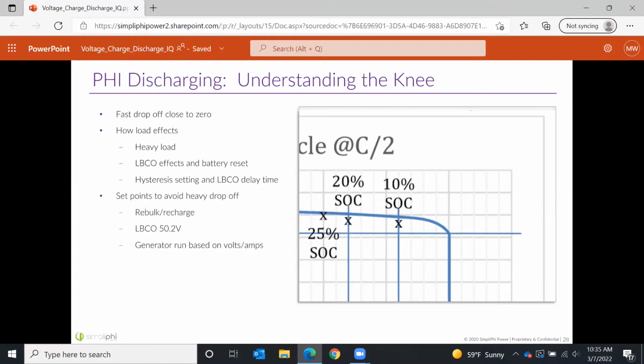The way to prevent this, realistically, we recommend stopping discharging at 20% state of charge remaining in your batteries. This would be about 50.2 volts, but does vary depending on the load. So we recommend setting your low battery cutout to 50.2 volts. If you've got to set it to 48 volts, then simply make sure your delay is very short on that cutout.